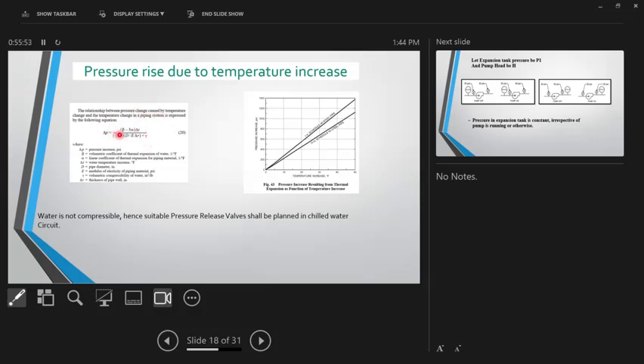This is the expression which talks about pressure changes caused by temperature. Now, don't worry much about this equation. The graph of this equation is plotted on the right-hand side. Imagine the change in temperature is, let's say, 20 degrees Fahrenheit, which is about 10 or 11 degrees centigrade. This can happen if you have a chilled water system operating at 6, 7 degrees centigrade, and over Saturday and Sunday the system is closed. You can expect the chilled water temperature to increase to ambient temperature. In your region, it could be 40, 50, I don't know. But in India, it could be 30, 35 degrees centigrade. So a 10, 12, 15 degrees centigrade rise is very, very possible.